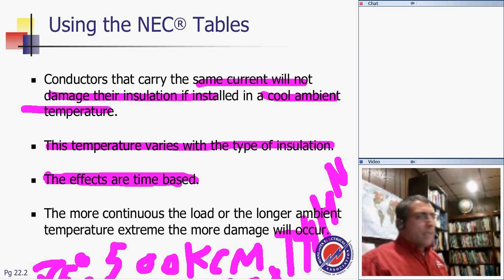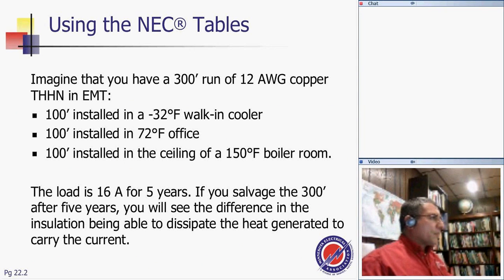The key point I want to give you, my friends, is that a conductor can carry a certain current based on the circumstances and the conditions. So if I ask you, Joe, about the same 500 kcmil conductor, if you put it in a cable tray, it's the same conductor in a cable tray, it will carry a completely different amount of amps. It would not carry 380. You put the 500 kcmil underground in a parallel circuit with 12 other ducts, it will be completely different amps. So the same conductor can carry different amps based on the configuration of that conductor.